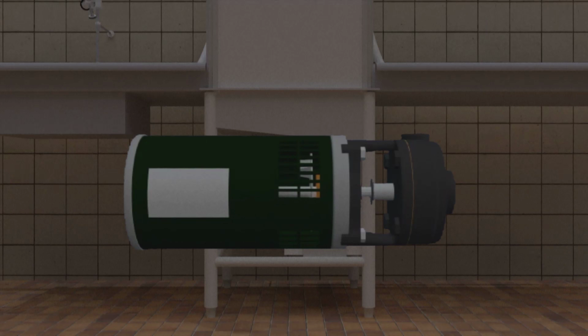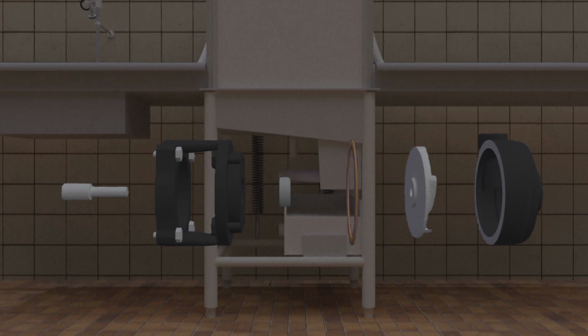The assembly is divided into two parts, the pump and the motor. The pump consists of a housing made of two halves. These two halves are bolted together with a gasket or O-ring to create a watertight seal. The front half is called the volute and directs water in and out of the pump, while the back half, called the base, offers stability to the pump's moving parts.